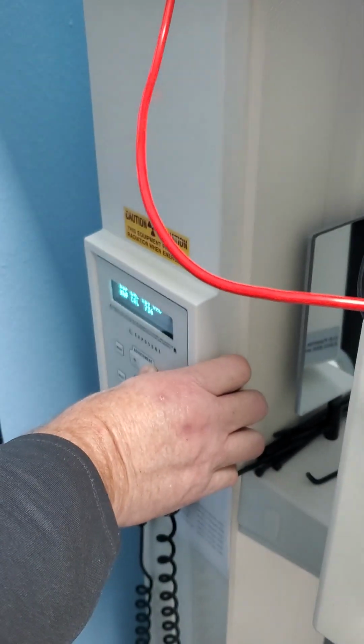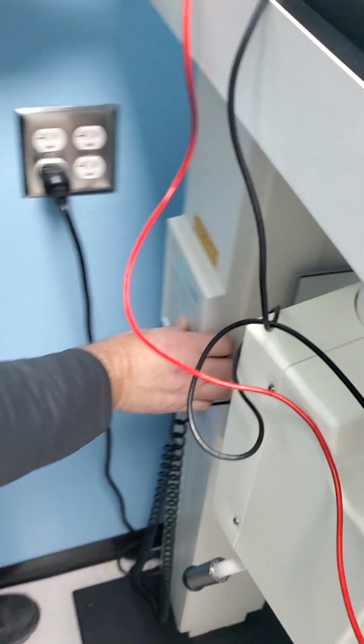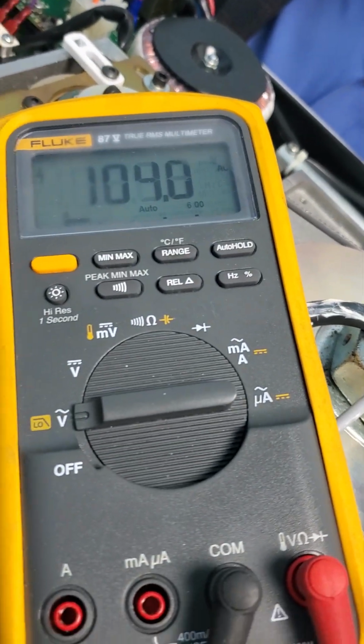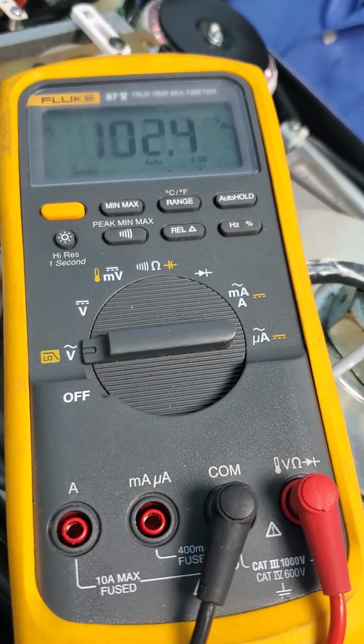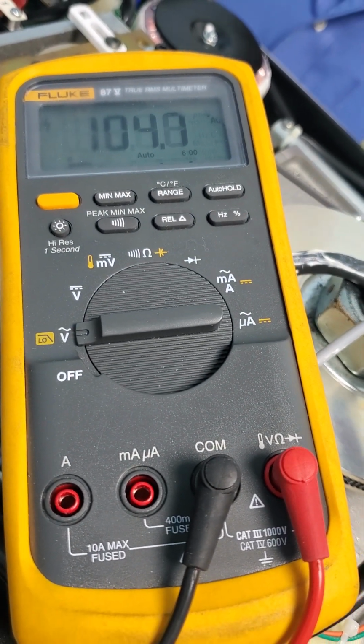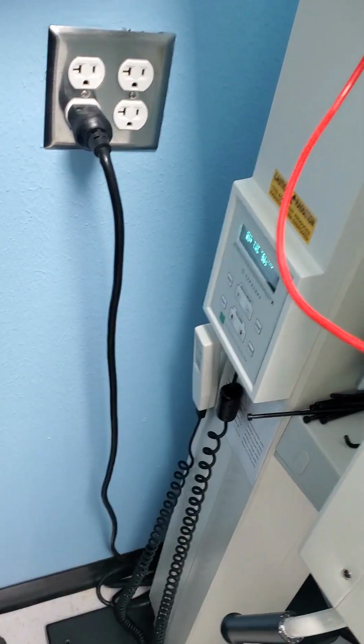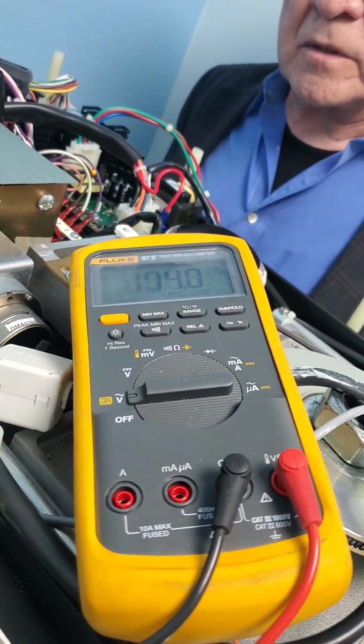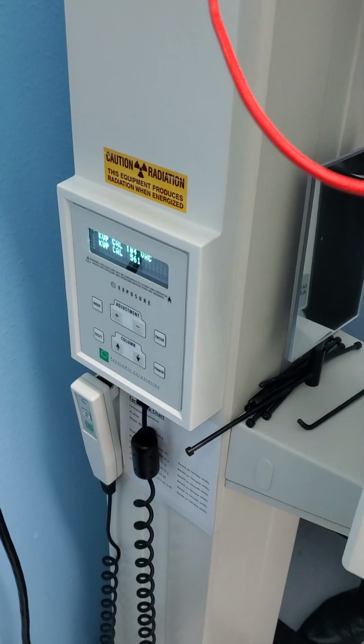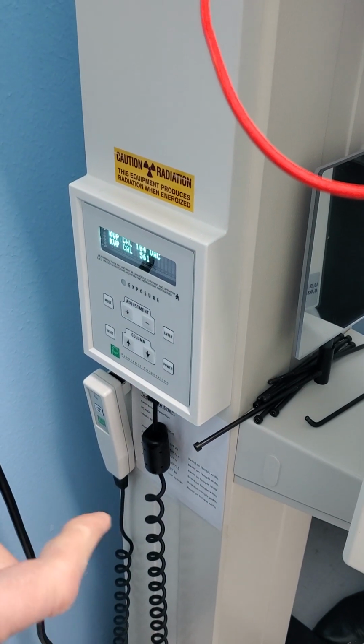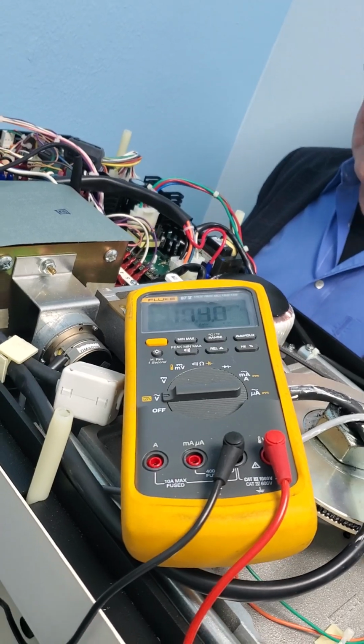Is this a second point check? Yeah. The first one was 89 volts. It's two points on the KV calibration. One is at 89 and one is at 104. Oh, I see. And is there a ramp between those two or something? It interpolates it itself. Okay, good. So there's our constant, and the number itself is not important other than it's what relates to what we should read here, which is 104.